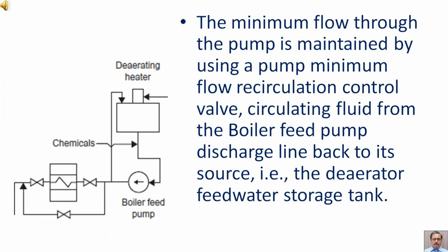This is the recirculation line and the recirculation control valve is located on this line. The minimum flow through the pump is maintained by using a pump minimum flow recirculation control valve, circulating fluid from the boiler feed pump discharge line back to its source — that is, the deaerator feed water storage tank.